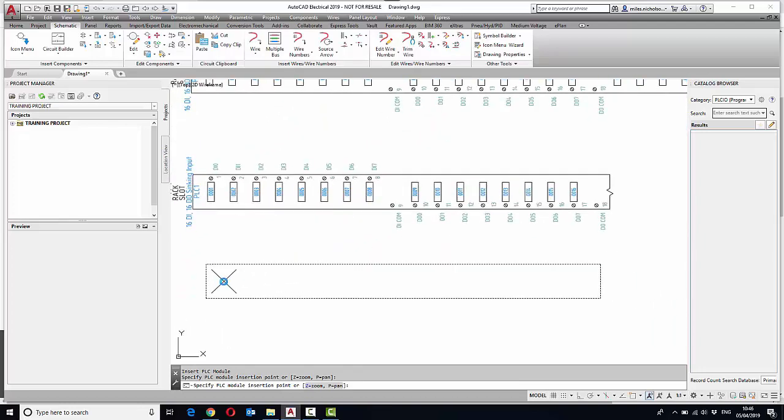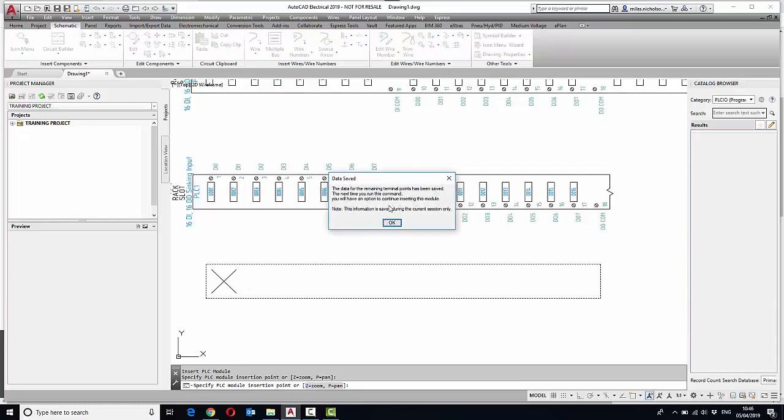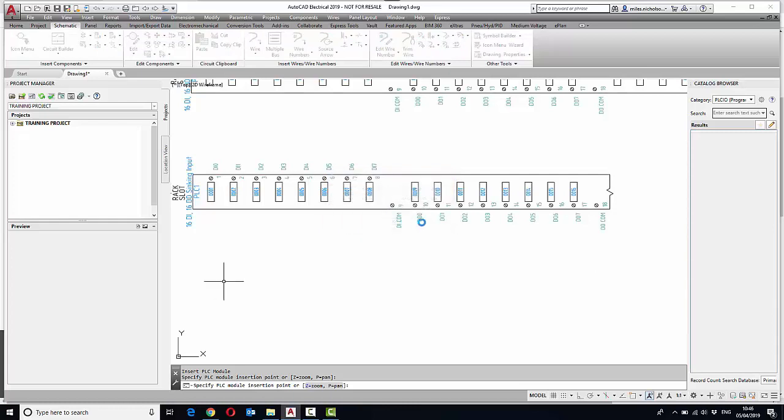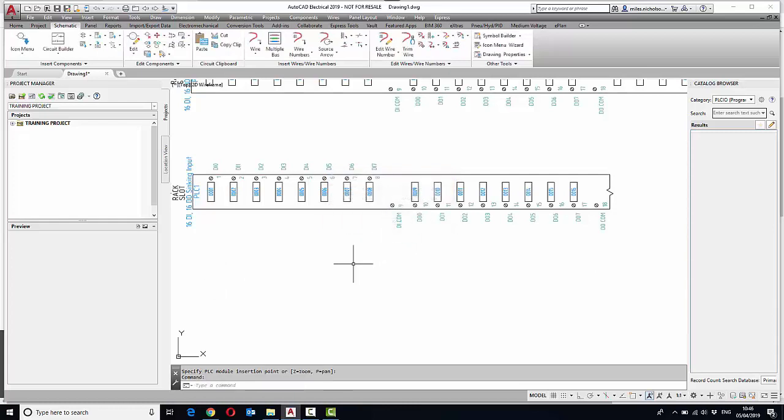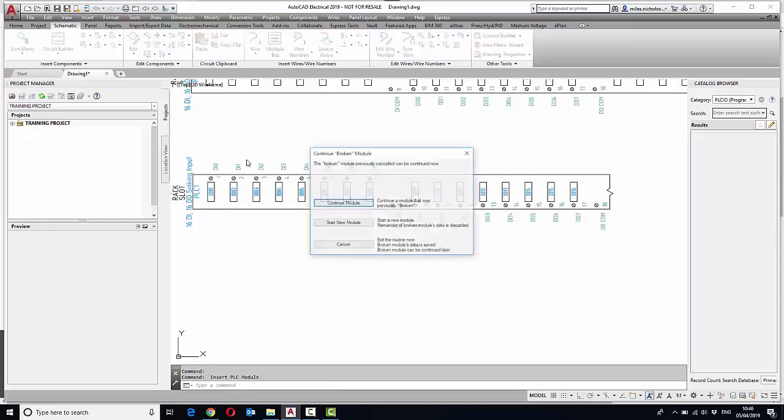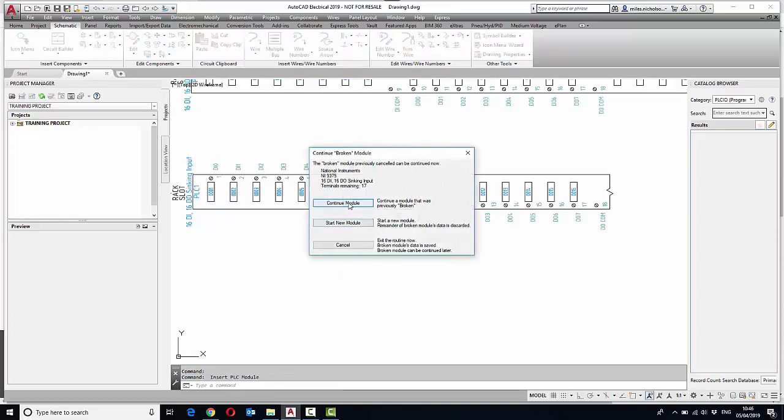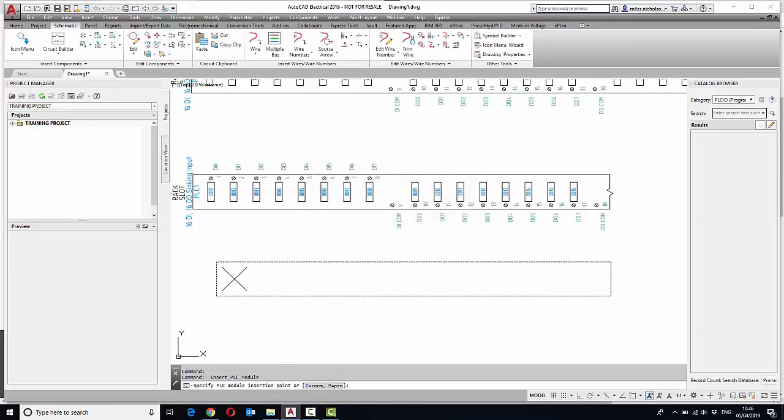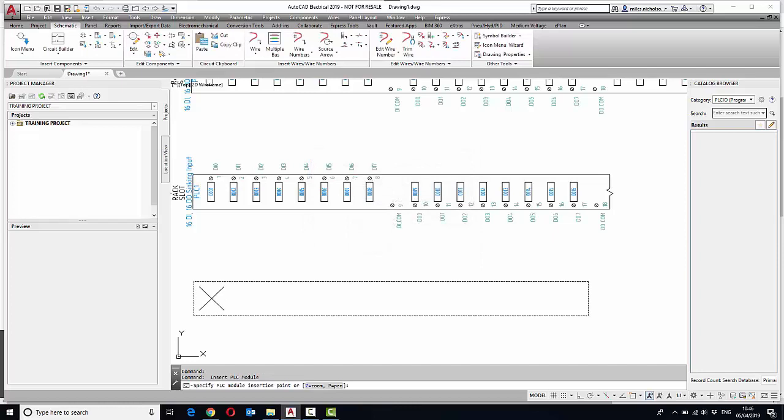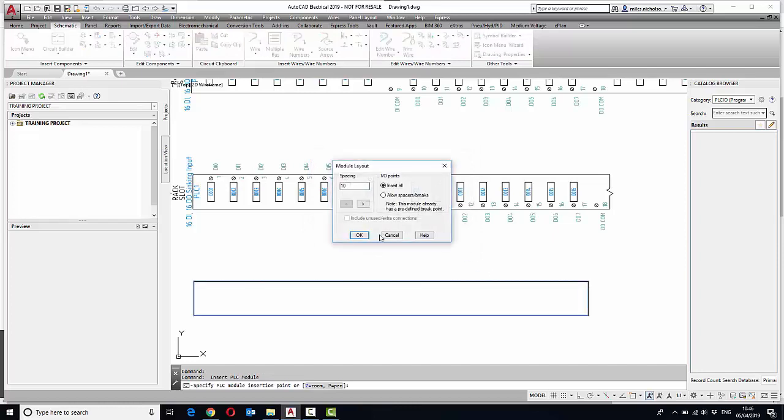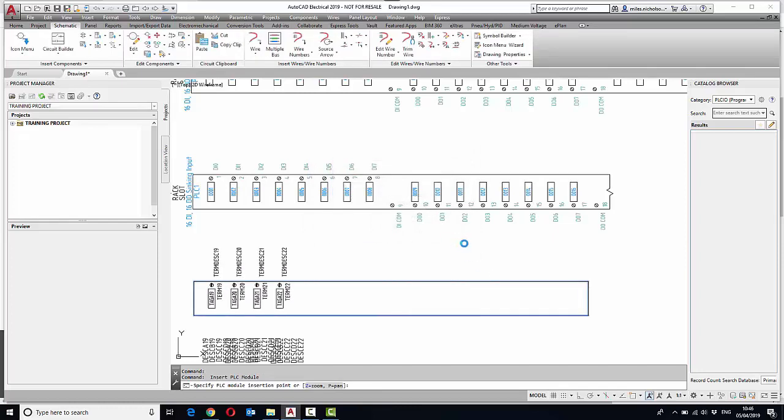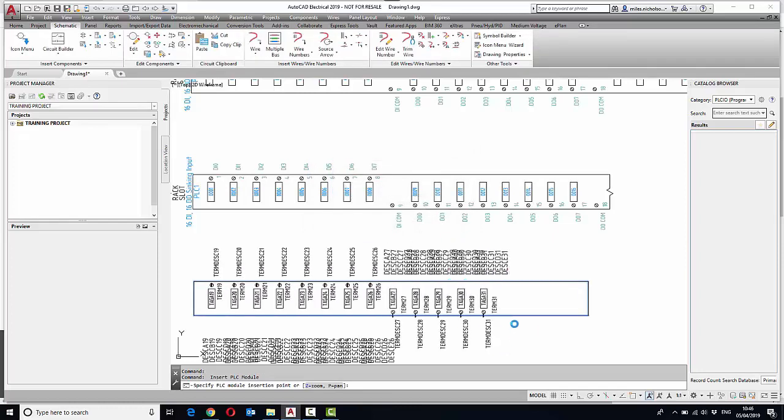If I escape out, the data for remaining points, terminal points, will be remembered within the session of AutoCAD. What that means is I could go into another drawing, I could select the PLC command, and then I can continue the module on a different page altogether if I wish.